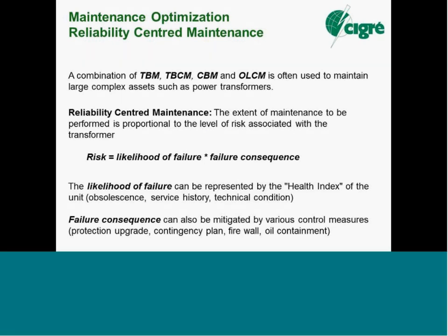In optimization, there's a bit of discussion in the guide about reliability-centered maintenance. It's really a basic way we implement reliability-centered maintenance when we talk about applying that to power transformers. It's not your classic RCM you might see with industrial processes. It's more about identifying risks for the transformer, the failure consequence and the likelihood of failure in deciding your maintenance effort. It's in combinations of time-based maintenance, time-based condition monitoring, condition-based maintenance and online condition monitoring, using an appropriate mix to affect economic outcomes.